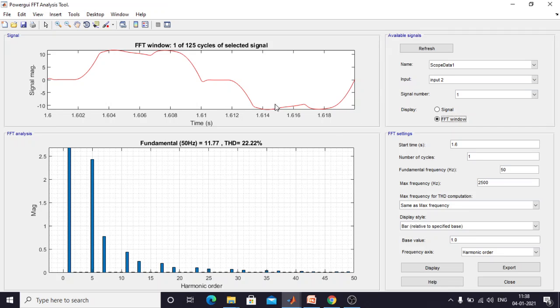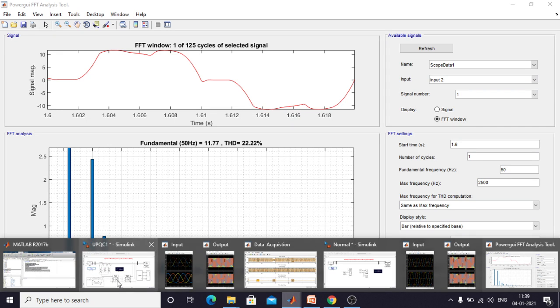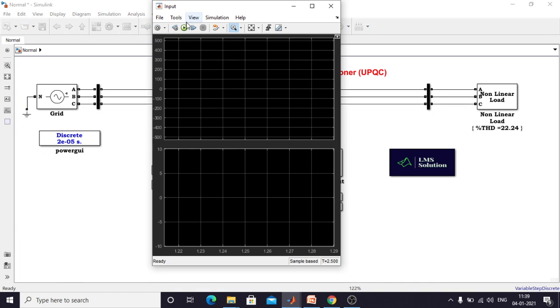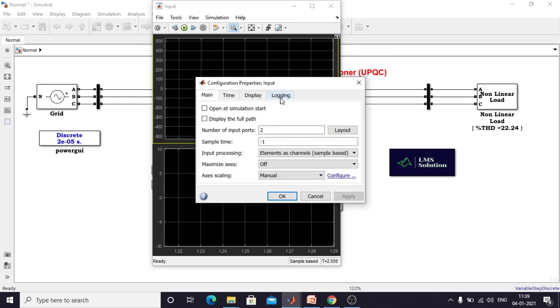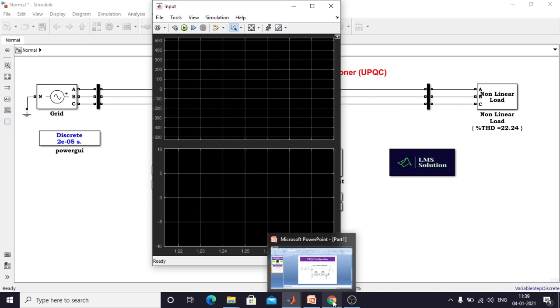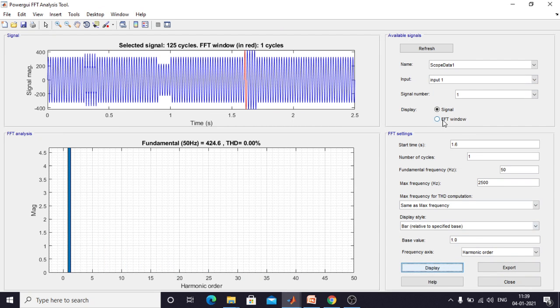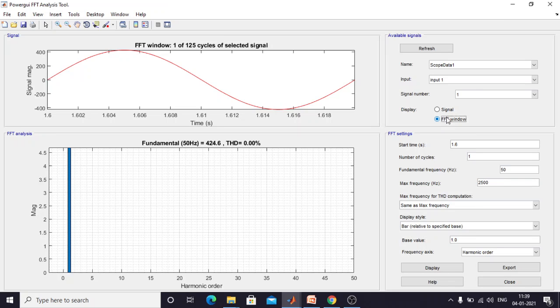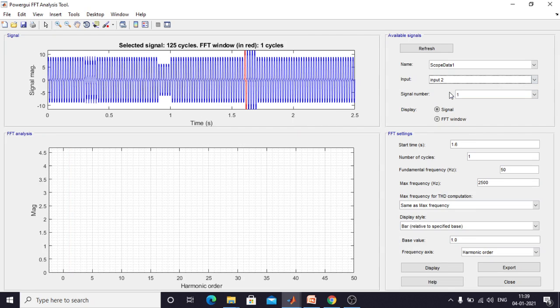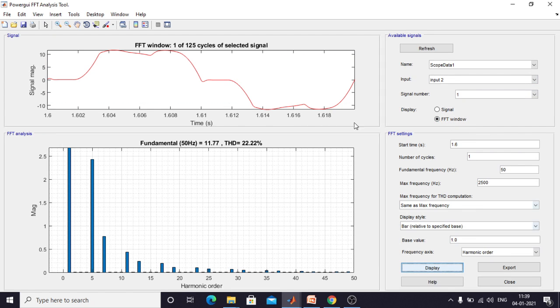Next we need to check the THD of that source current. Now you can see that the THD of the source current is around 22.2 percent. The input voltage THD is around 0. The input current THD is around 22.2 percent. This is the normal operation of the power system without using any power quality improvement device.